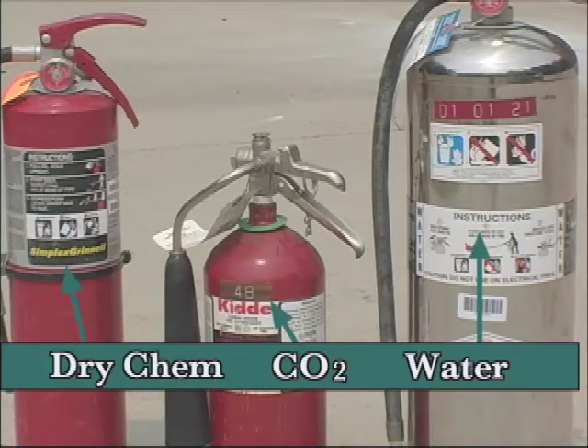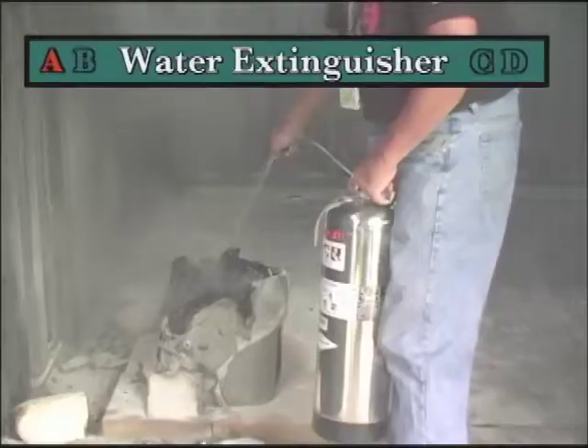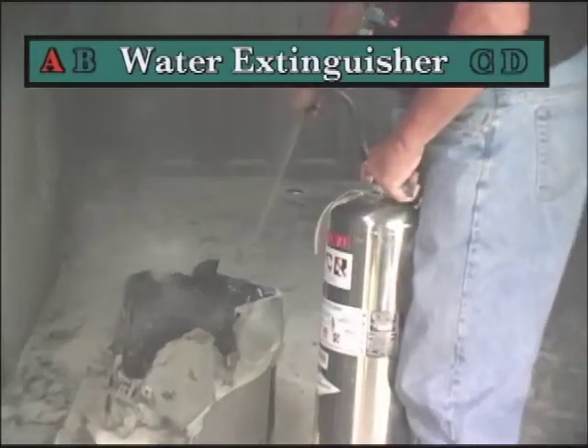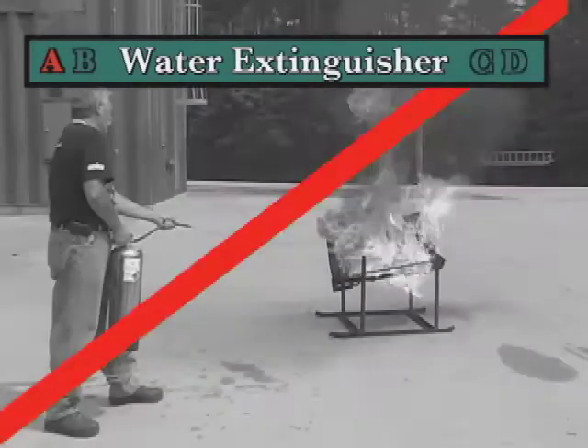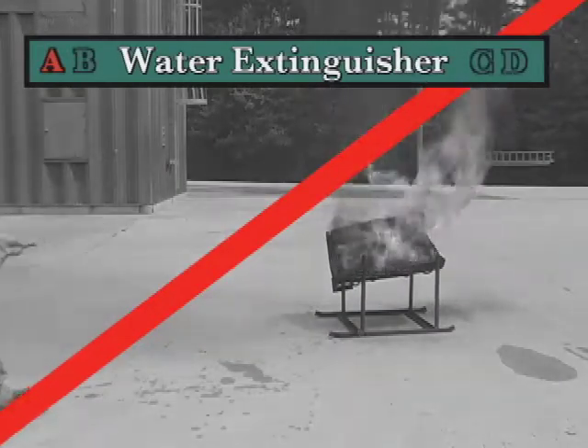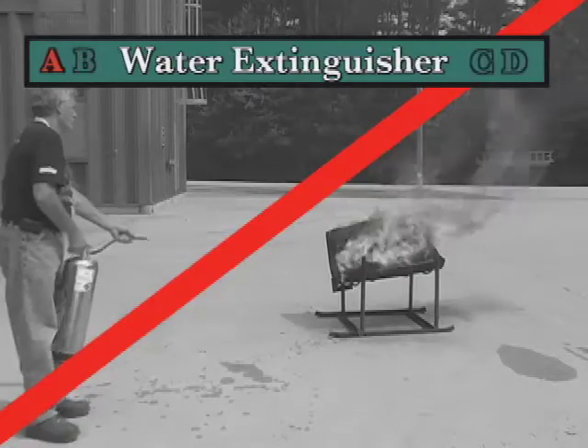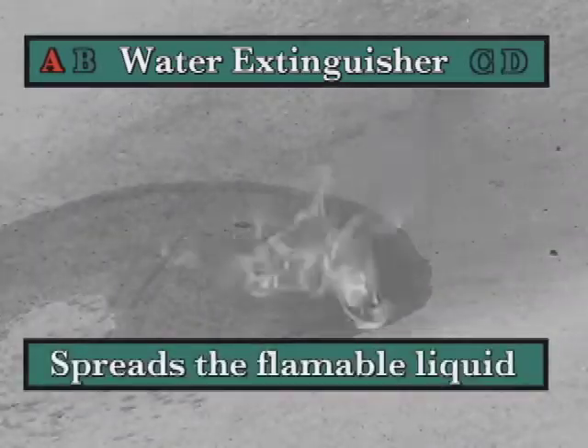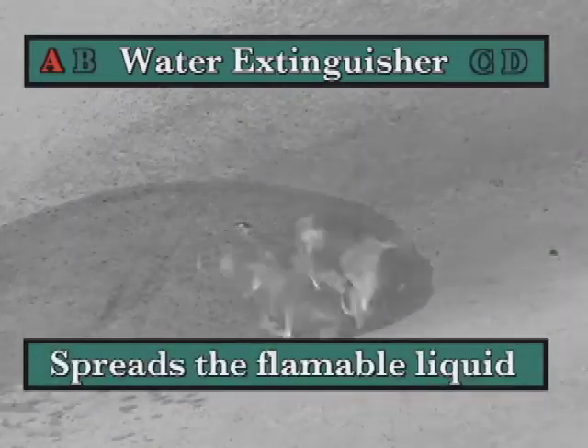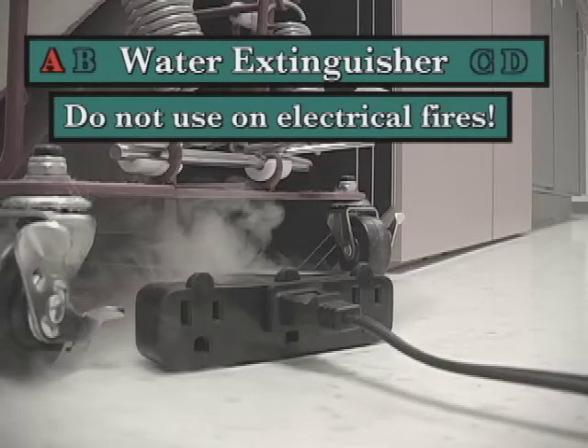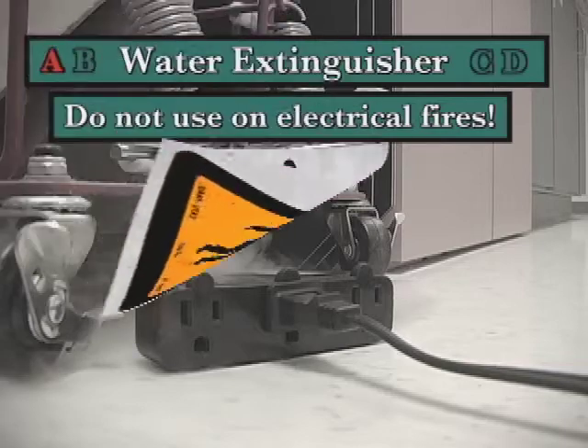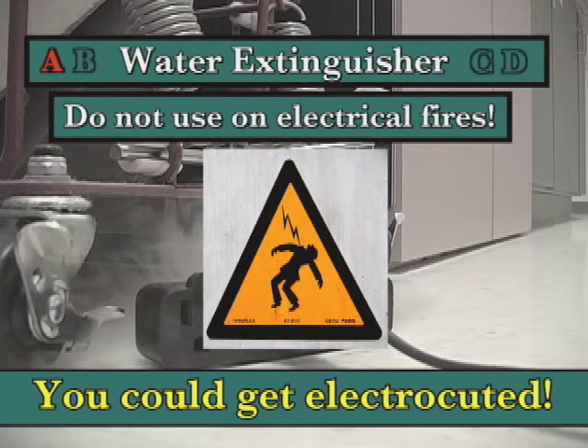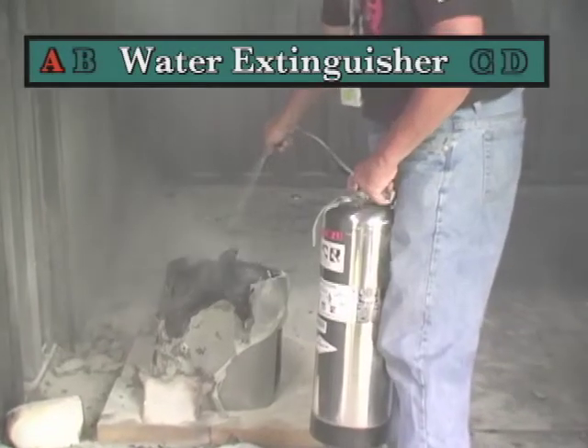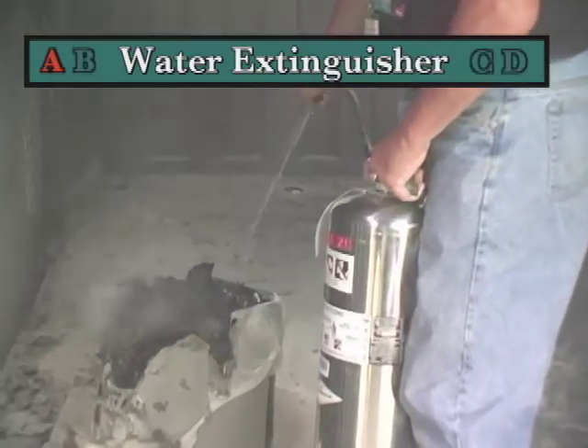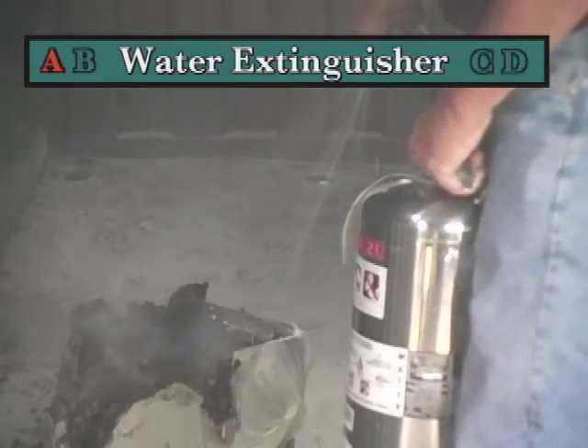There are 3 common types of extinguishers. Water extinguishers are suitable for Class A fires only. It's dangerous to use a water extinguisher on burning liquids such as gasoline or grease because the water will only spread the fire around, and it won't put it out. Water won't put out an electrical fire either, and the stream of water will conduct electricity right to you. You could be electrocuted.